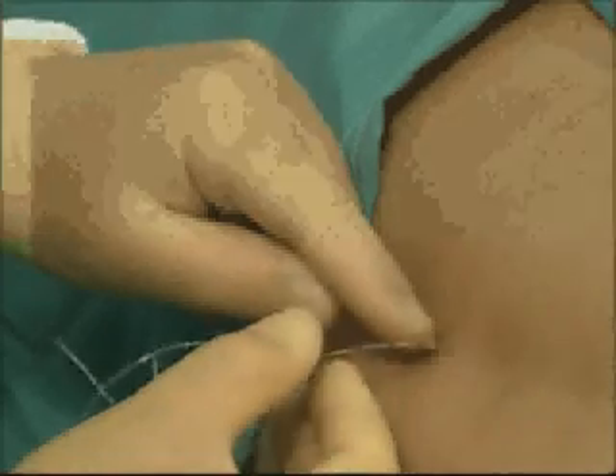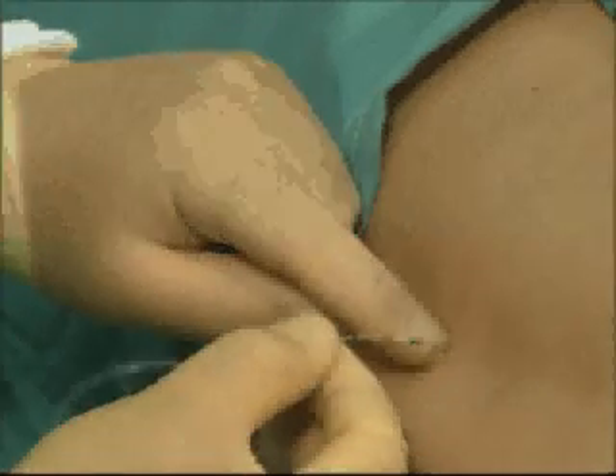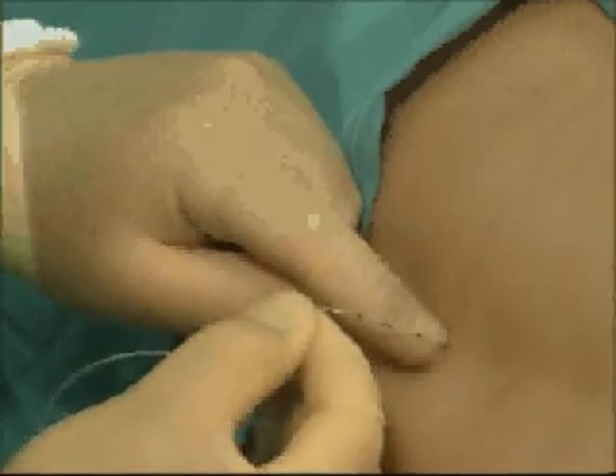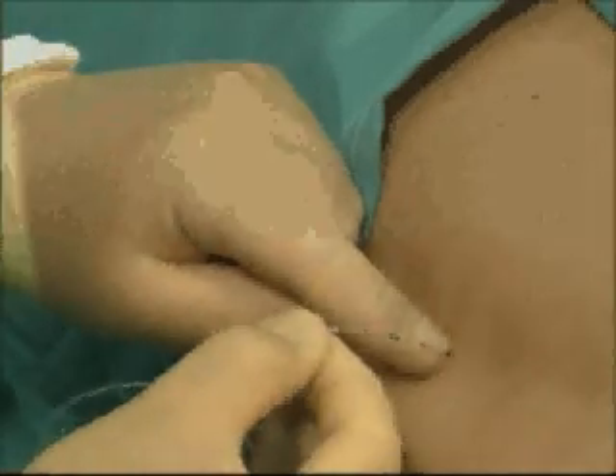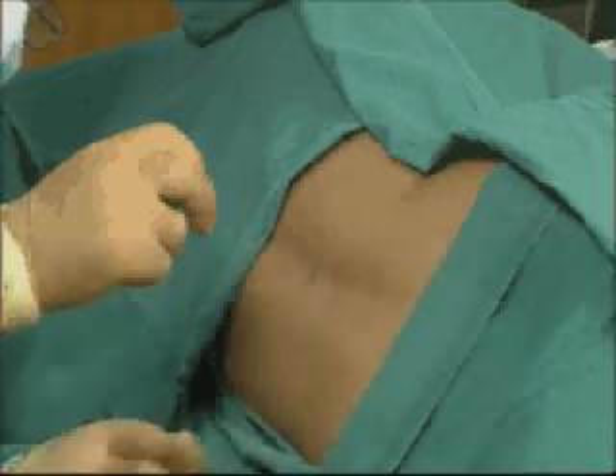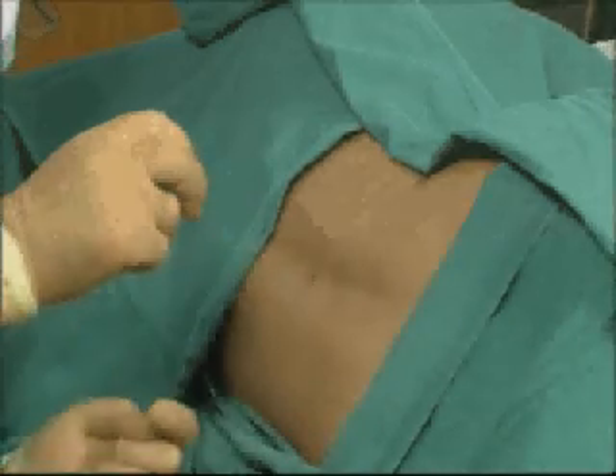The catheter is carefully withdrawn to leave sufficient length within the epidural space, typically 3 to 4 centimeters. To confirm that the catheter lies correctly within the epidural space, the Shah test is performed. The catheter is first lowered and then raised, whilst the behaviour of the meniscus is observed. Any fluid or blood which flows back also indicates that the catheter is in the wrong position.